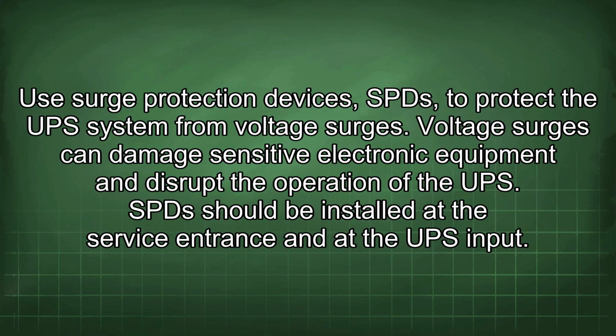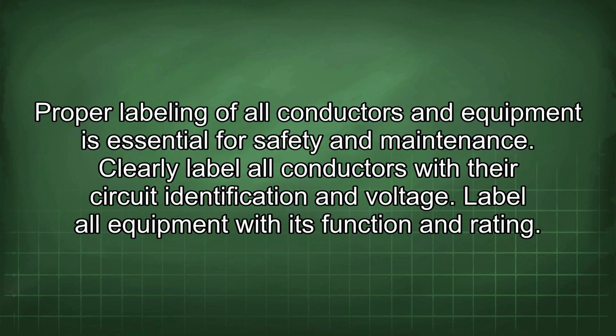Use surge protection devices, SPDs, to protect the UPS system from voltage surges. Voltage surges can damage sensitive electronic equipment and disrupt the operation of the UPS. SPDs should be installed at the service entrance and at the UPS input. Proper labeling of all conductors and equipment is essential for safety and maintenance. Clearly label all conductors with their circuit identification and voltage. Label all equipment with its function and rating.